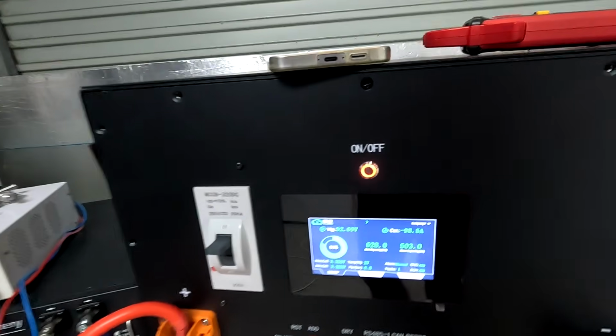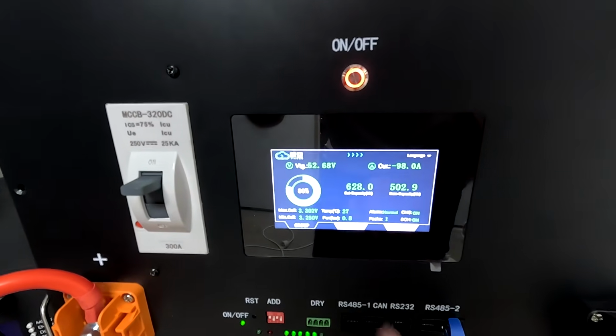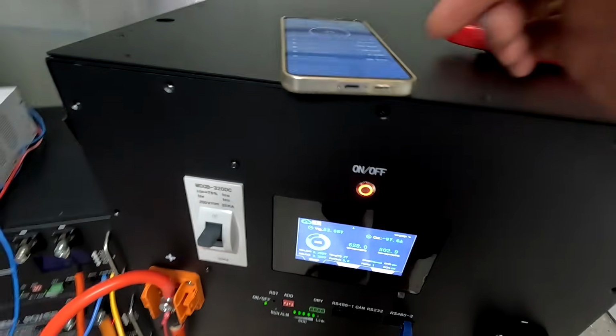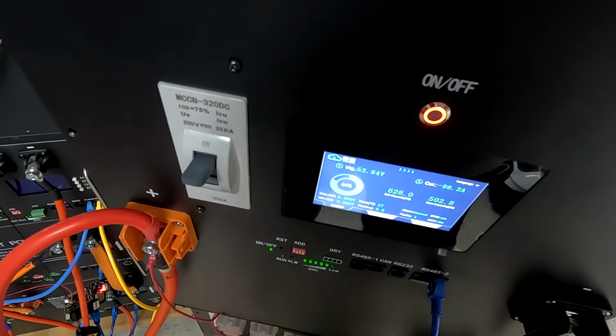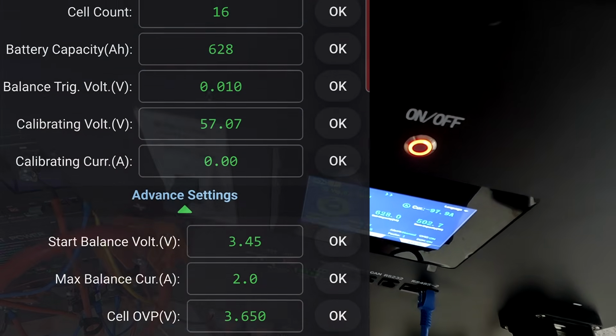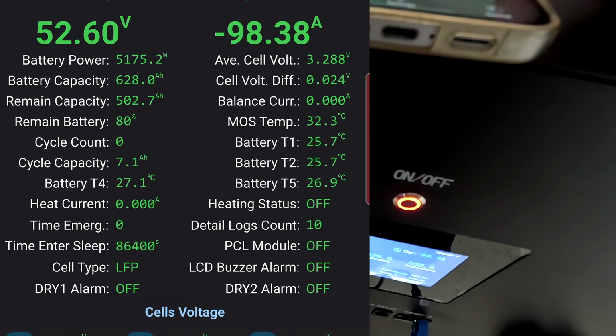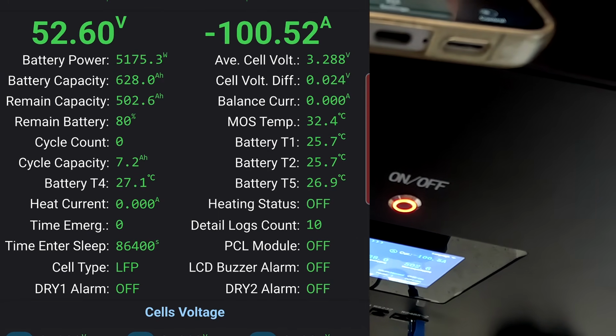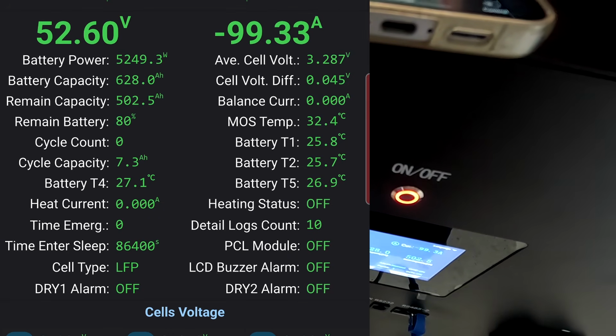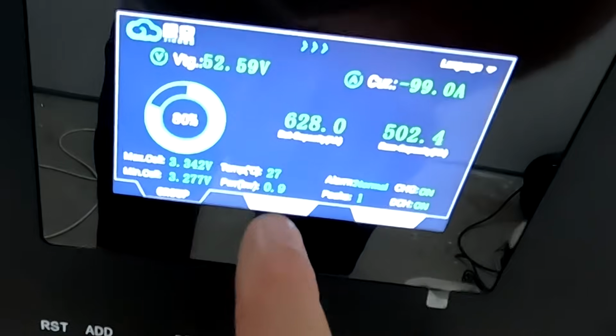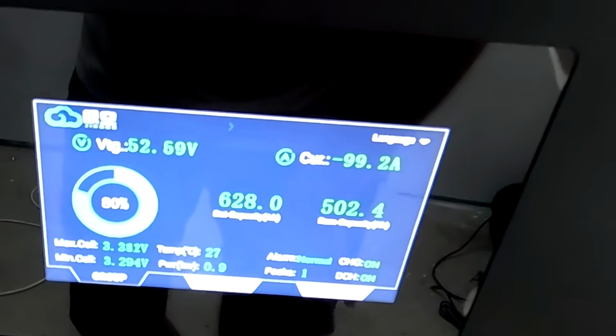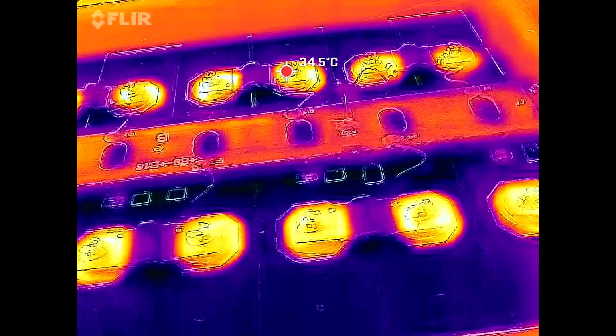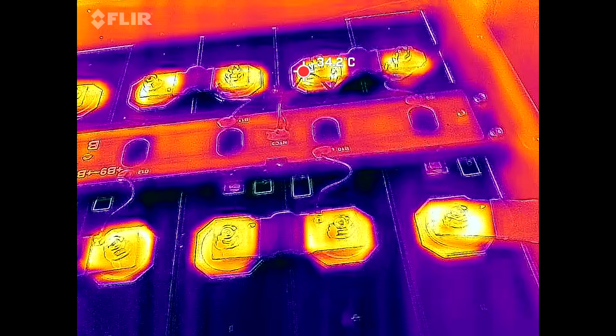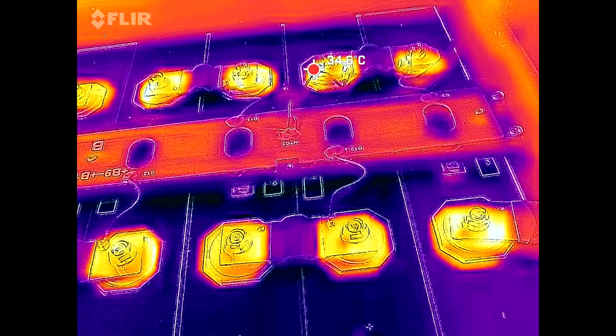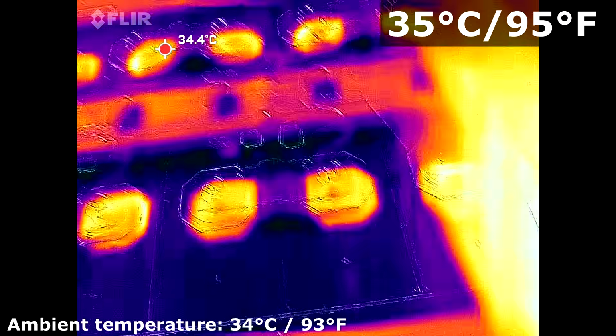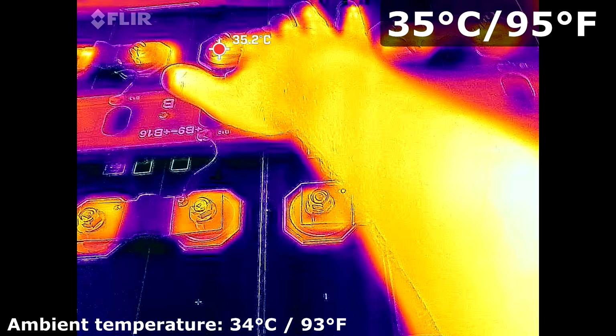And we also want to monitor the temperatures in this BMS here, what we are measuring. So the highest temperature, no, hang on. We go into the JK app. There we go. And here we can see all the temperatures, 25, 26, 27. 27 is the highest. And this is what it shows here as well on the display. That's how we start. Right, let's have a quick look how the battery is performing after a couple of minutes with 100 amps. We can see the bus bar here at 35 degrees. But when I touch them, they feel actually cold.